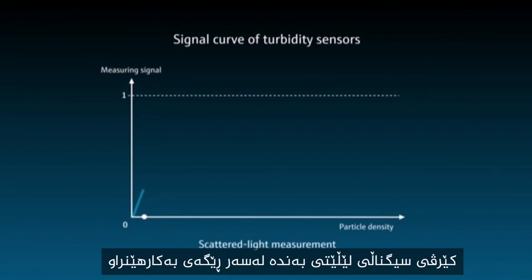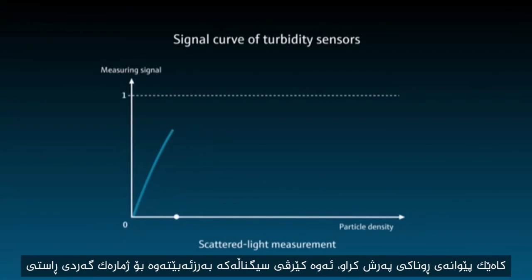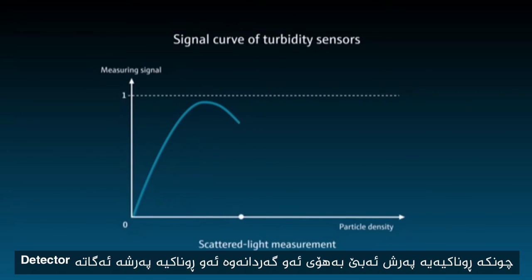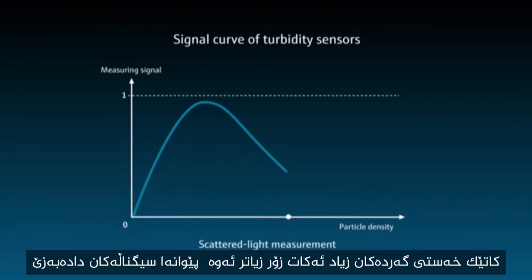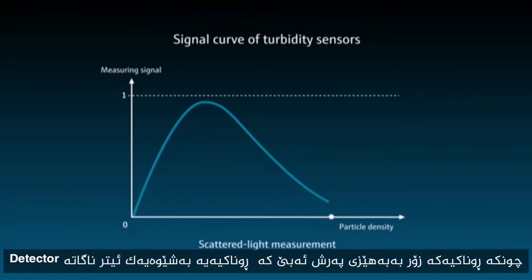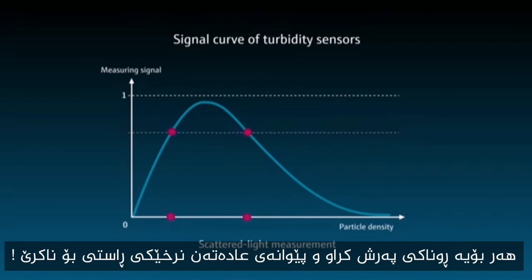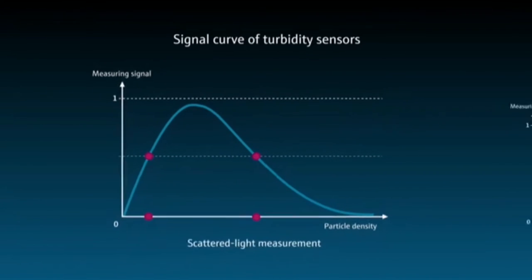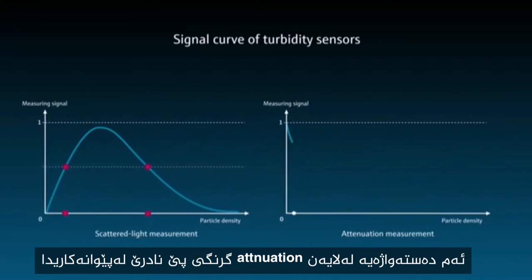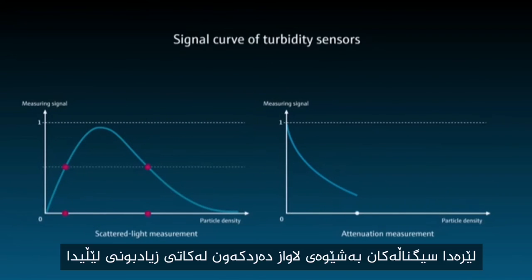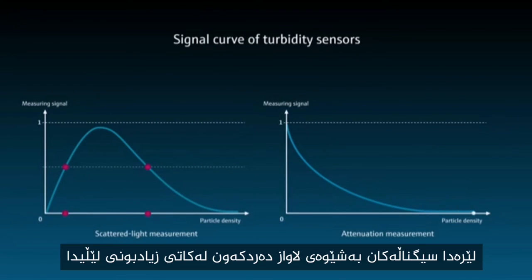The signal curve of turbidity sensors depends on the method used. When using scattered light measurement, the signal curve rises up to a certain particle density because the light is scattered towards the detector. When the particle density increases further, the measuring signal weakens again because the light is scattered so strongly that the radiation no longer reaches the detector. That's why scattered light measurement does not always deliver clear results. This phenomenon does not occur with attenuation measurement — here the signal consistently weakens with increasing turbidity.